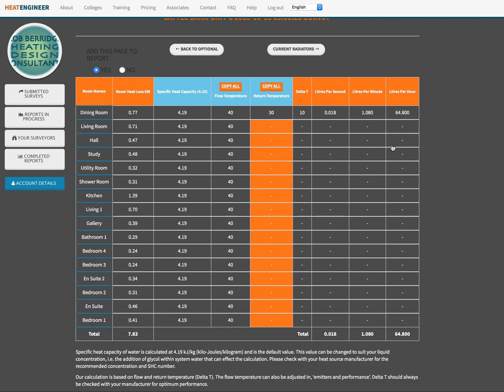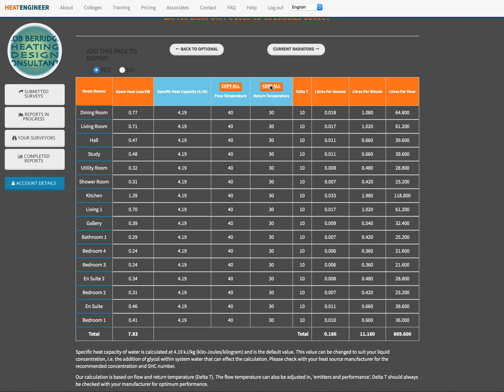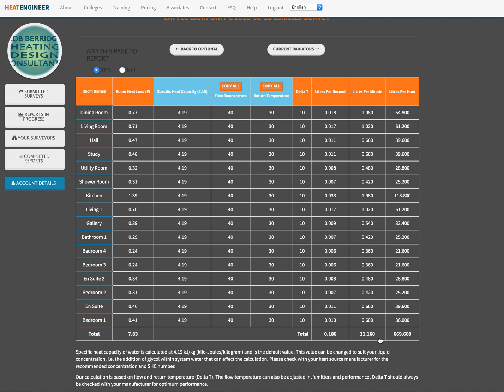Now the good thing about this, how we've done this now, because it's all populated from the heat loss calculation that you've done, so everything is calculated from that so it's very bespoke. All your totals are building up down here now. If we copy all to get everything into that, there we go. Now we can see that it's populated every little area that we've got now, so each individual one. So for each individual area you can balance to get the correct flow rate for each area, but also what you can do with the total figure there, this is going to help you start sizing your primary pipe work, it's going to help start sizing your pumps.